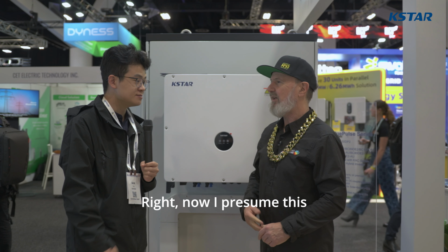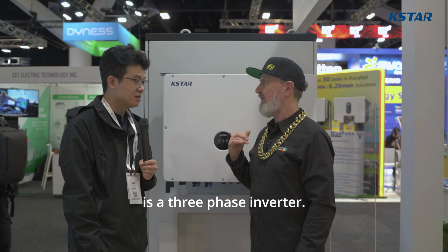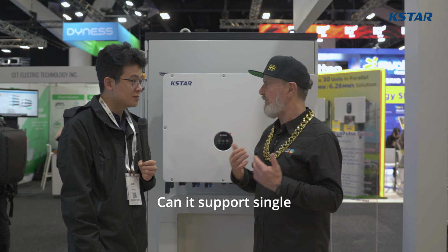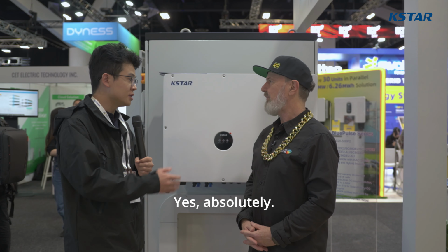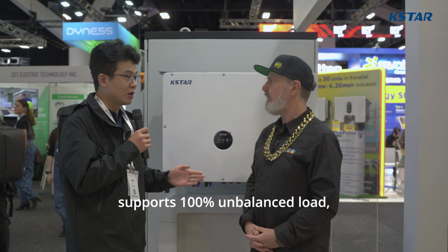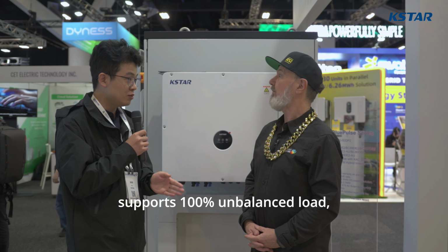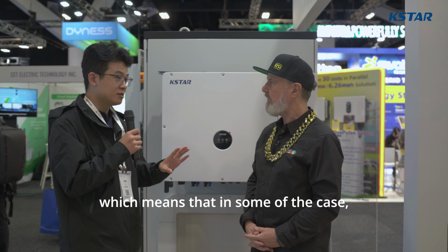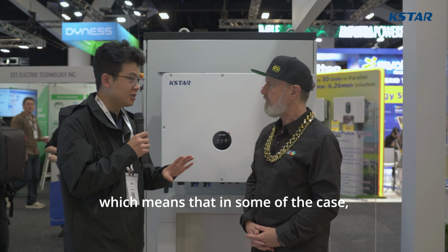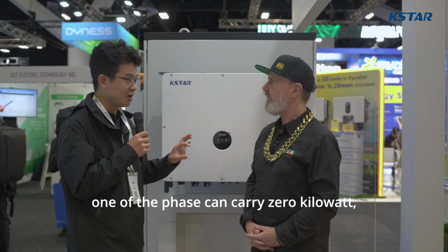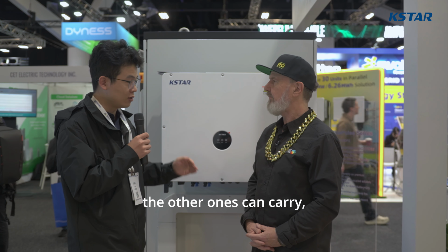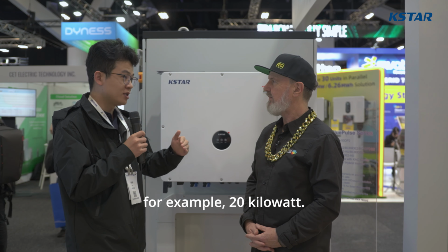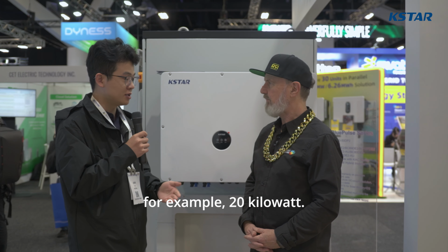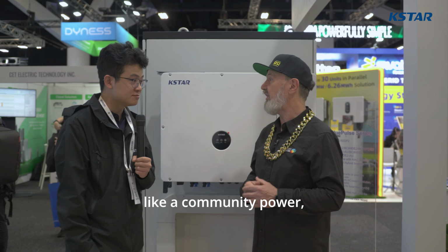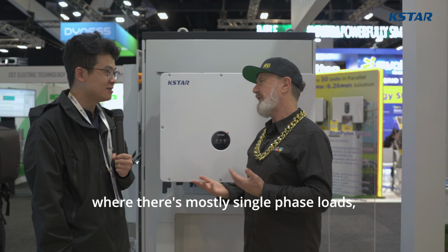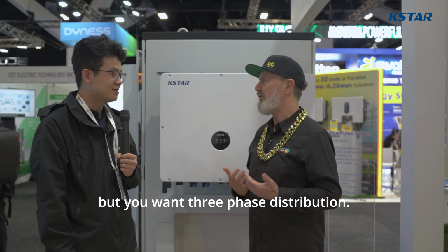Right. Now, I presume this is a 3-phase inverter. Can it support single-phase loads as well? Yes, absolutely. This one supports 100% unbalanced load, which means that in some cases, one of the phases can carry 0 kilowatts, and the other ones can carry, for example, 20 kilowatts. Very useful for things like community power, where there are mostly single-phase loads, but you want 3-phase distribution.